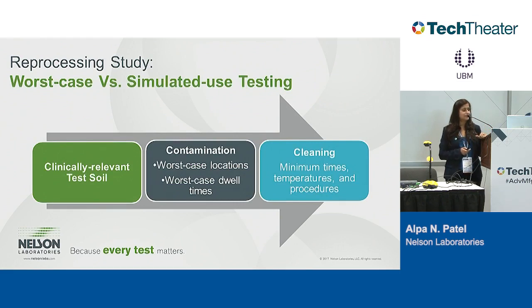When you do these validations, you always want to consider worst case devices and worst case testing. What I mean by that is you want to use clinically relevant soils that are considered worst case. You also want to test locations that are worst case, dwell times that are worst case, which I'll go into in detail as we go further. And in the cleaning side of it, you want to use minimum times, temperatures, and procedures as well.